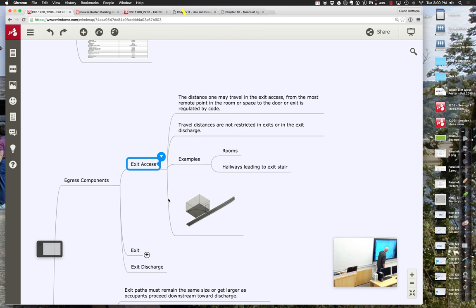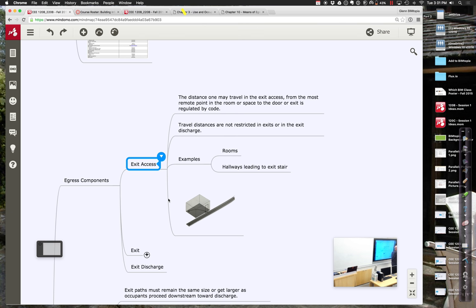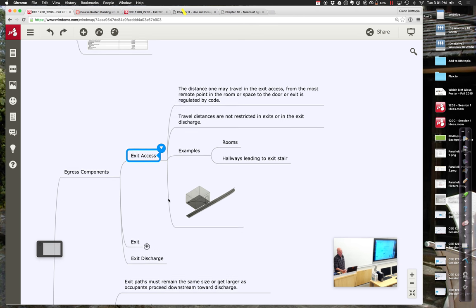The exit access distance is limited by code — it could be a room or a hallway. What's considered the exit is interesting: it could be a doorway going outside, or in the case of a multi-story building, just getting you to an enclosed fire-safe stairway. The limit is roughly 200 linear feet for an unsprinklered building, or 250 linear feet for a sprinklered building. If longer than that, we must provide a second means of exit — it's always good to have more than one, in case a pathway is blocked.